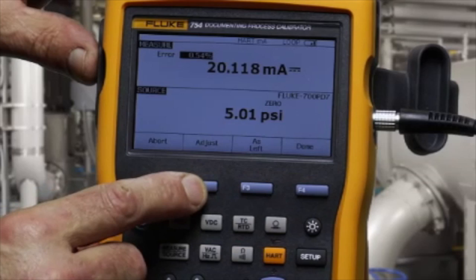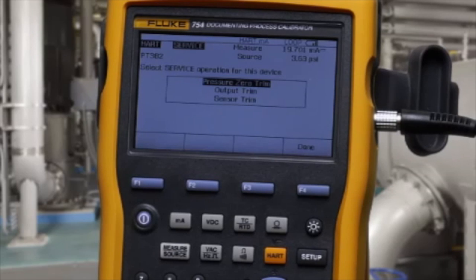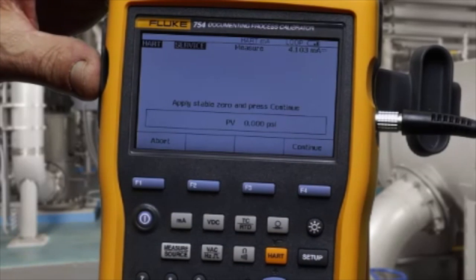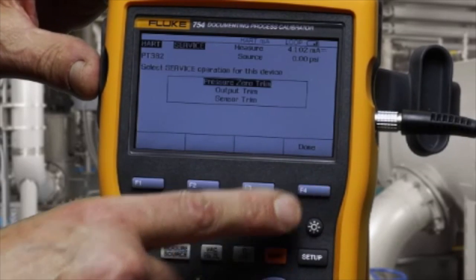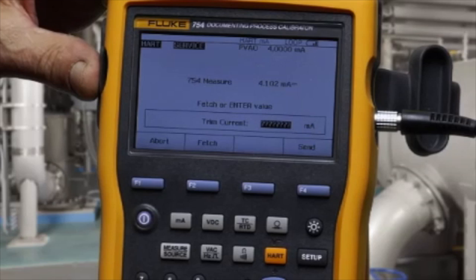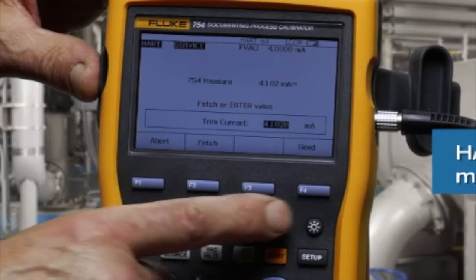Next select adjust and first perform a pressure zero trim with the pump vented to atmosphere. And then an output trim where we trim the milliamp output by fetching a four milliamp value as measured and send the trim to adjust.